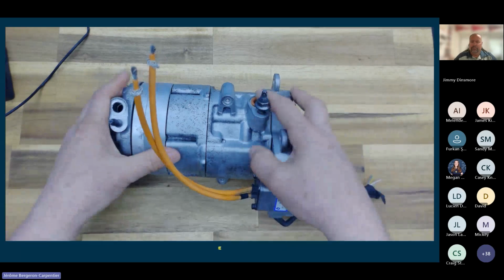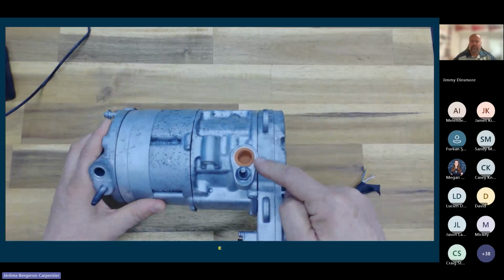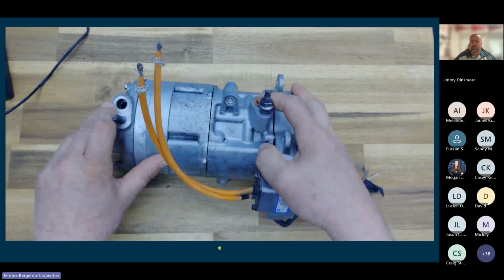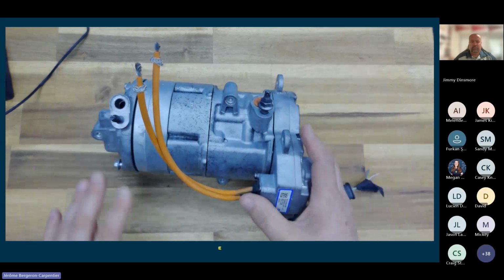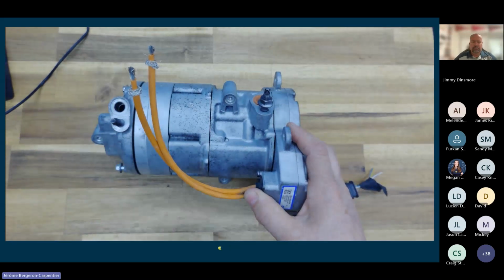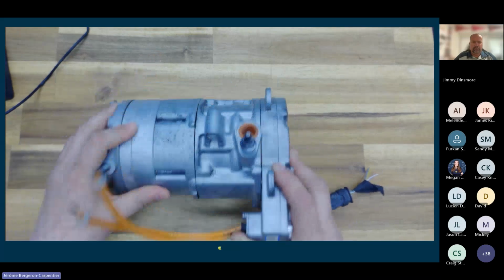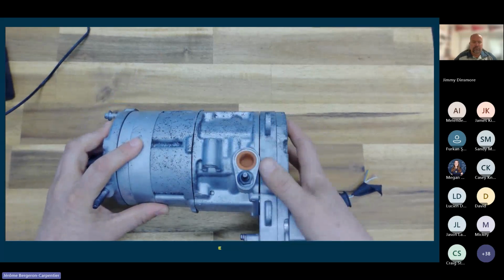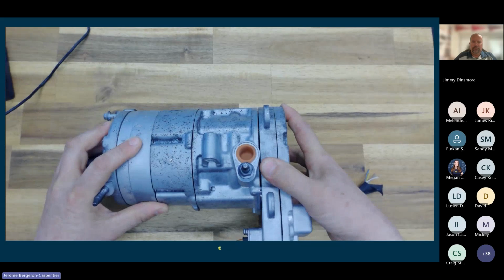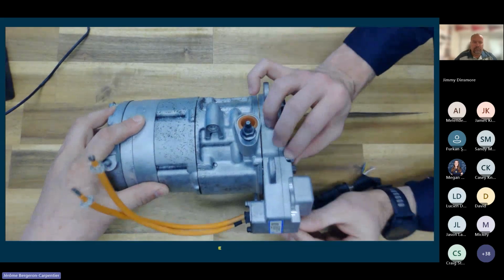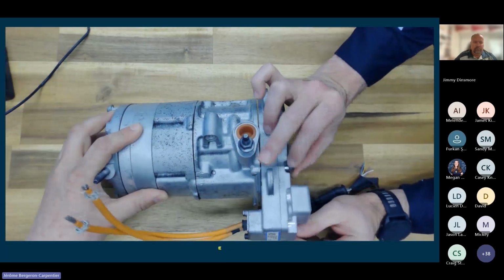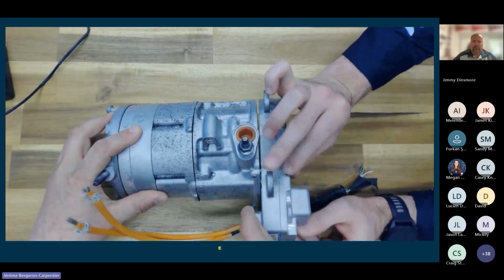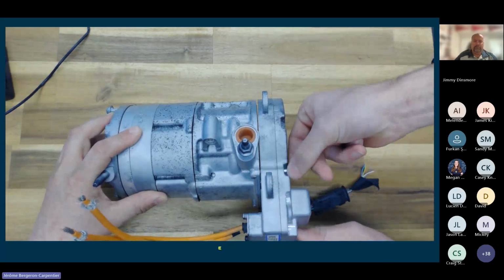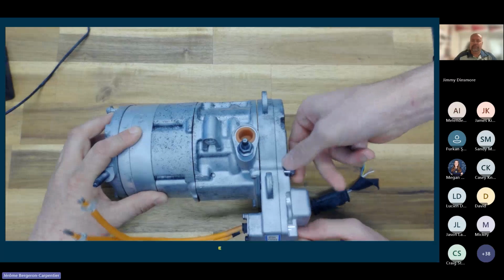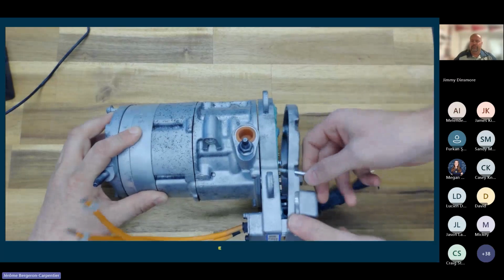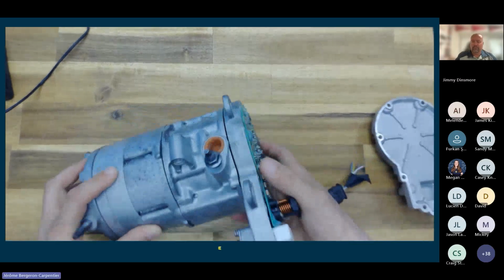One thing I want to point out, though, is you're going to see we have the low side port here, and we have the high side discharge port. One unique thing about a lot of these electric AC high voltage compressors is the low side is usually very close to the electronics in the unit itself. So you're going to take out the last 2 bolts here. And that's to keep the electronics cool. There are a few things you're going to see very quickly with this unit: you'll see the electronics here, the board.